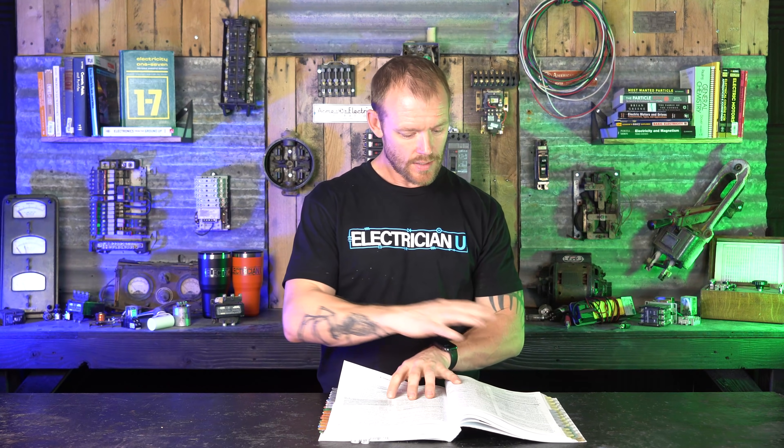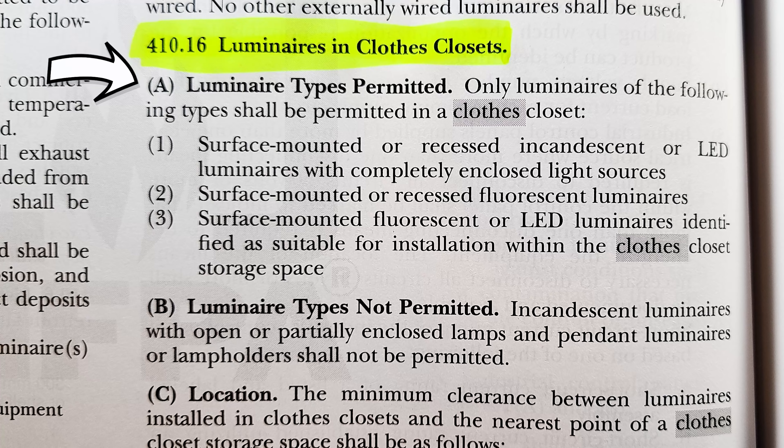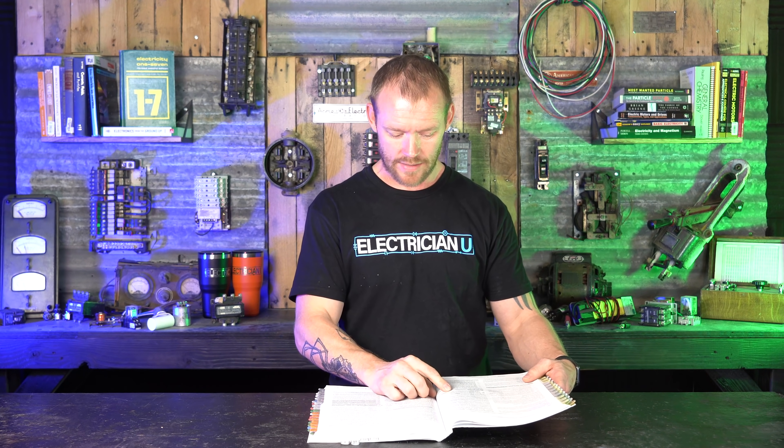If we open up NEC Article 410 about putting lighting in closets, there have been some changes in the last few years. At 410.16 we have luminaire types permitted — and not permitted. In closets, only luminaires of the following types shall be permitted: surface-mounted or recessed incandescent or LED luminaires with completely enclosed light sources — that's the key. Number two, surface-mounted or recessed fluorescent luminaires. And surface-mounted fluorescent or LED luminaires identified as suitable for installation within the clothes closet storage space. You can no longer have a keyless fixture with an incandescent or halogen bulb inside a closet. If it is incandescent, it must be surface-mounted or recessed with a completely enclosed light source, meaning clothing can't come in contact with a super-hot light bulb.